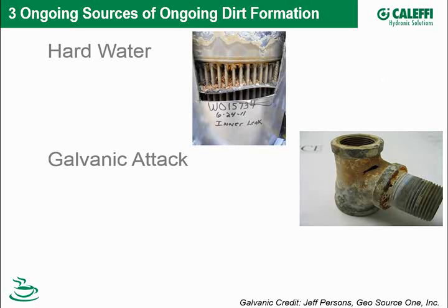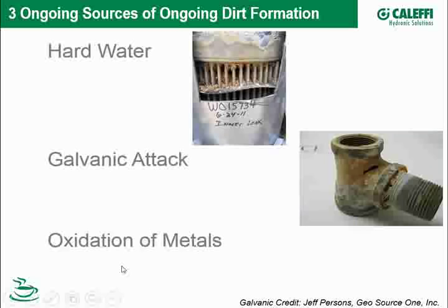We did webinars on hard water in the past — check our archive for more detail. The second category is galvanic attack. Whenever you have metals that are largely different on the elemental scale of nobility — for example, a brass nipple and a steel T connected together — and you have water with conductive elements in it, you can set up galvanic attack.